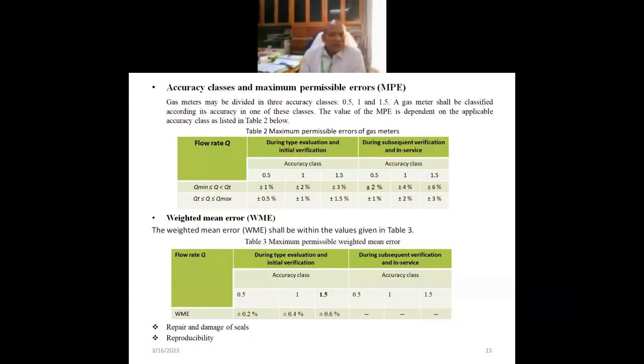And another term is weighted mean error, WME. The weighted mean error shall be within the values as per table 3, and flow rate Q and accuracy class 0.5, it is for the evaluation and initial verification, WME should be plus minus 0.2%, and for class 1 accuracy it is plus minus 0.4%, and for 1.5 accuracy class it is 0.6%.